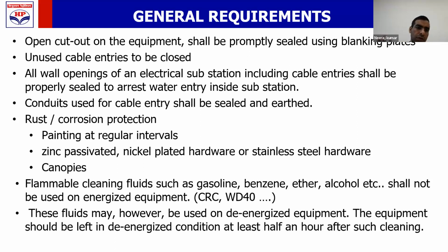Cable entries shall be closed. Wall openings on the substation shall be closed. Conduit used for cable entry shall be sealed. These are all normal requirements we all follow. Now, what needs to be done for rust and corrosion prevention. Painting should be done at regular intervals. Zinc passivated, nickel plated hardware or steel hardware may be used.